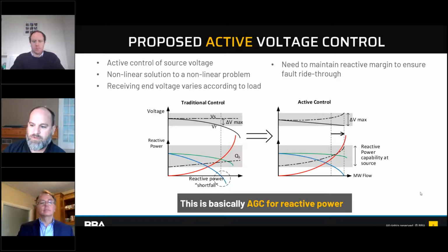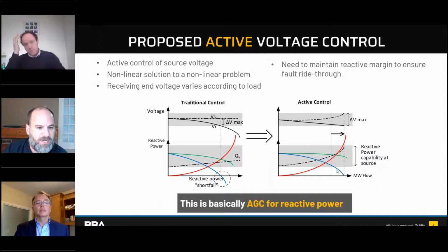So instead of a linear increase of Q with straight voltage at the output of the generator or source, you have a nonlinear V which results in a nonlinear reactive power output. Now you've basically eliminated your reactive power shortfall and freed up your ability to run more power across the system more dynamically. All you've really done is given yourself voltage headroom, building the regulation characteristic into your voltage control scheme.